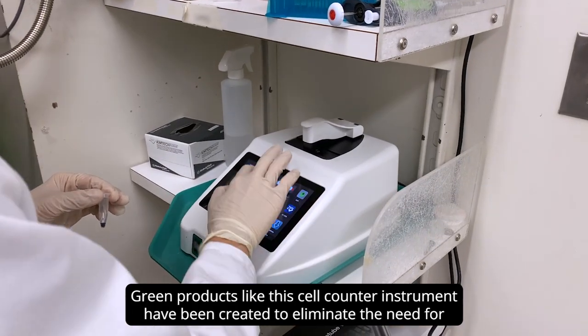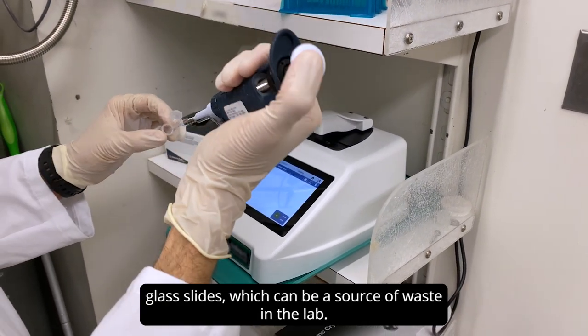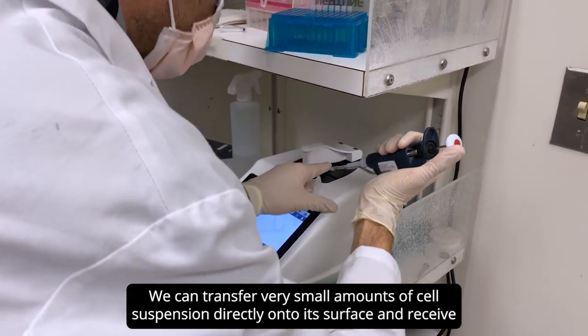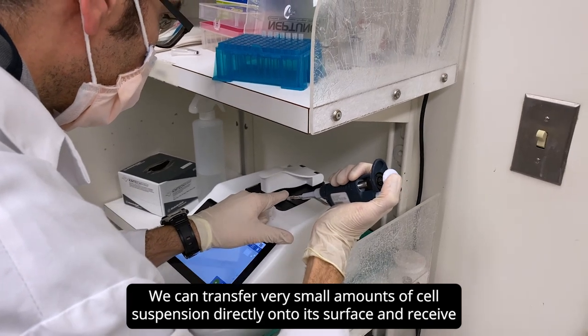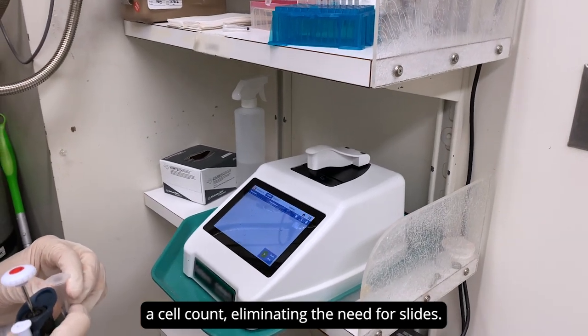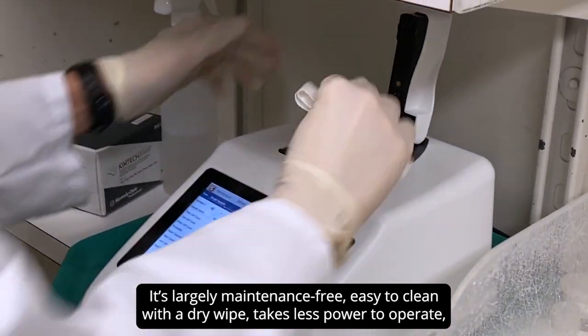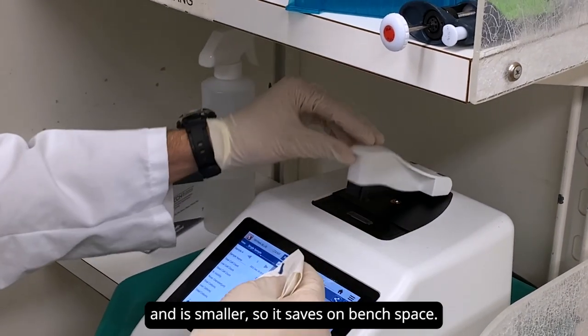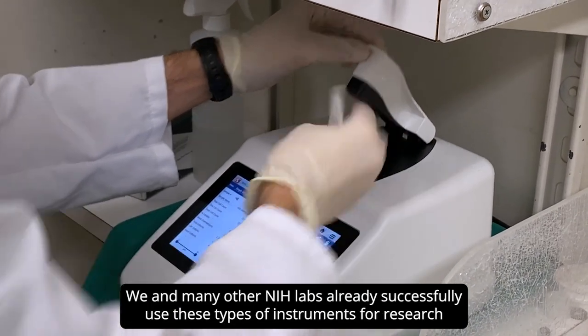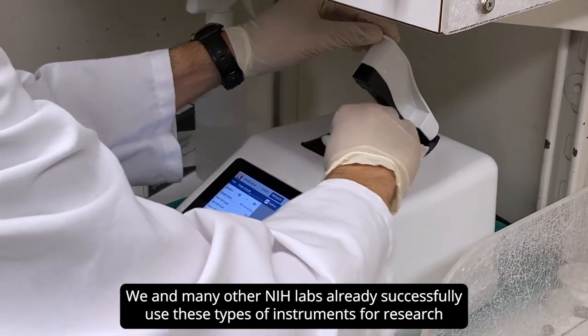Green products like this cell counter instrument have been created to eliminate the need for glass slides, which can be a source of waste in the lab. We can transfer very small amounts of cell suspension directly onto its surface and receive a cell count, eliminating the need for slides. It's largely maintenance-free, easy to clean with a dry wipe, takes less power to operate, and it's smaller so it saves on bench space. We and many other NIH labs already successfully use these types of instruments for research purposes.